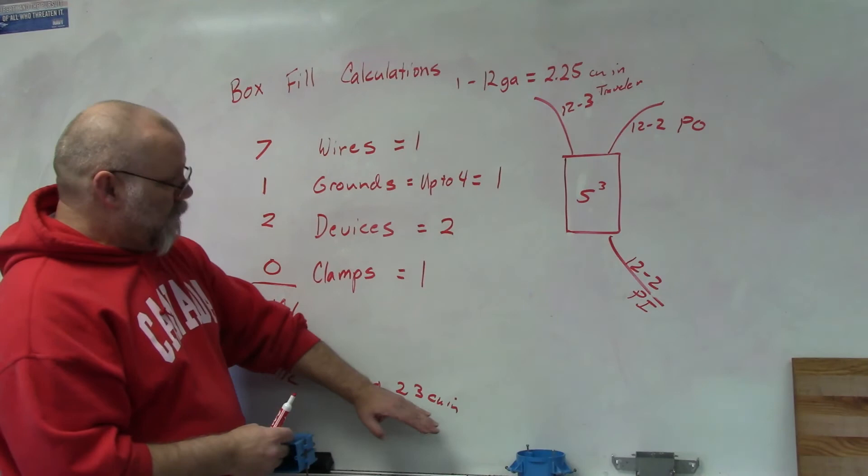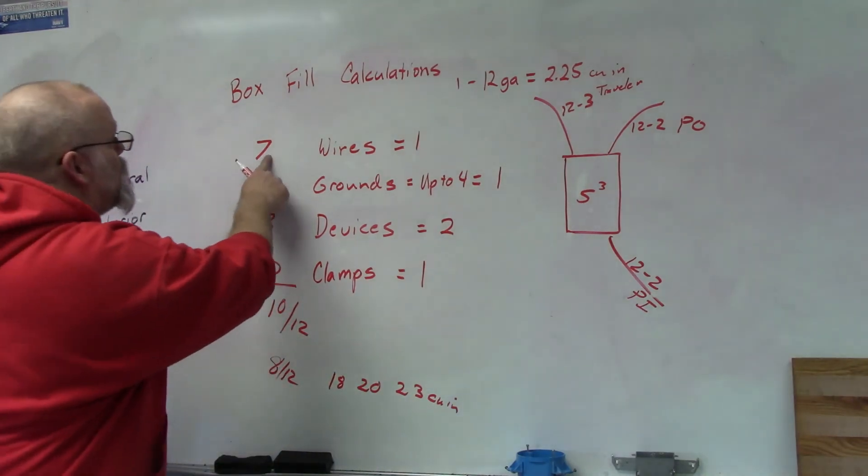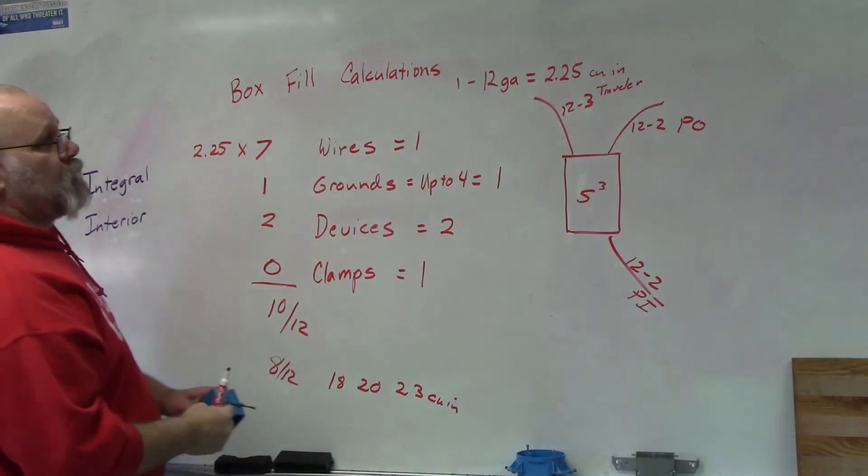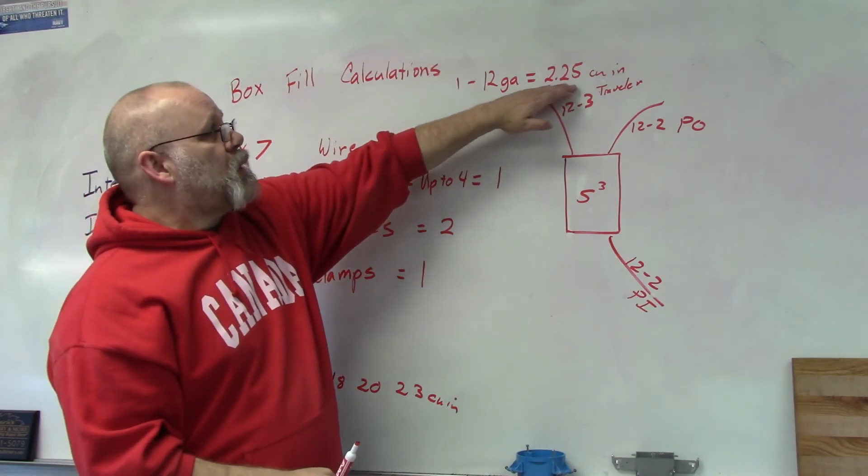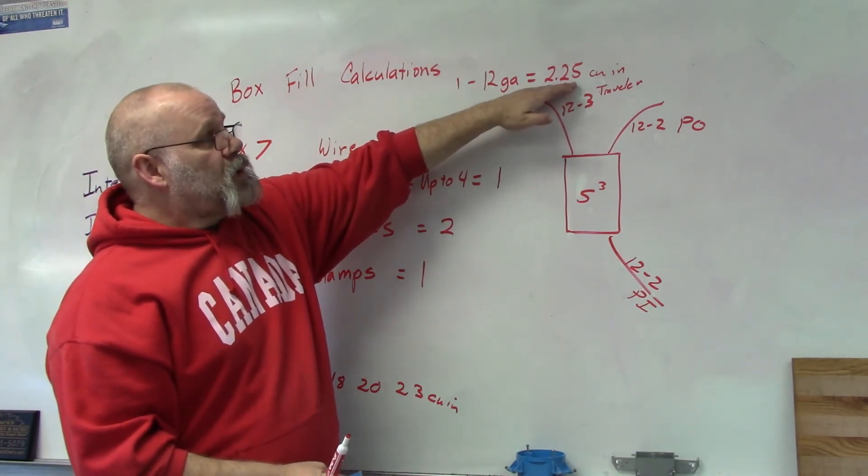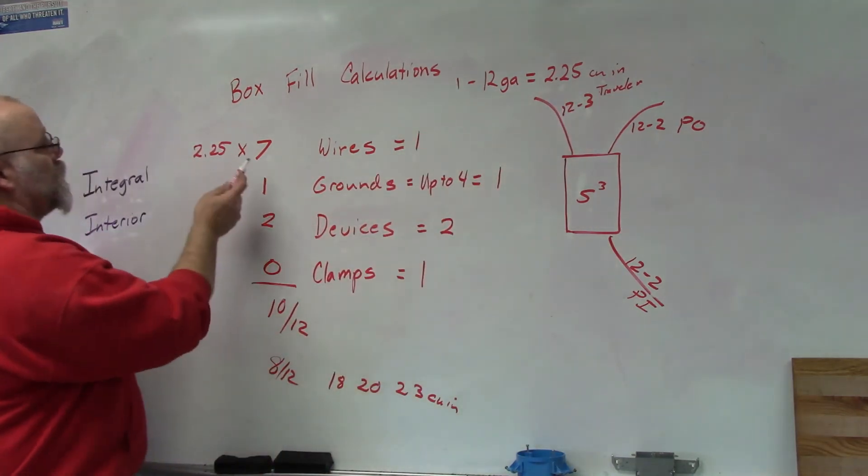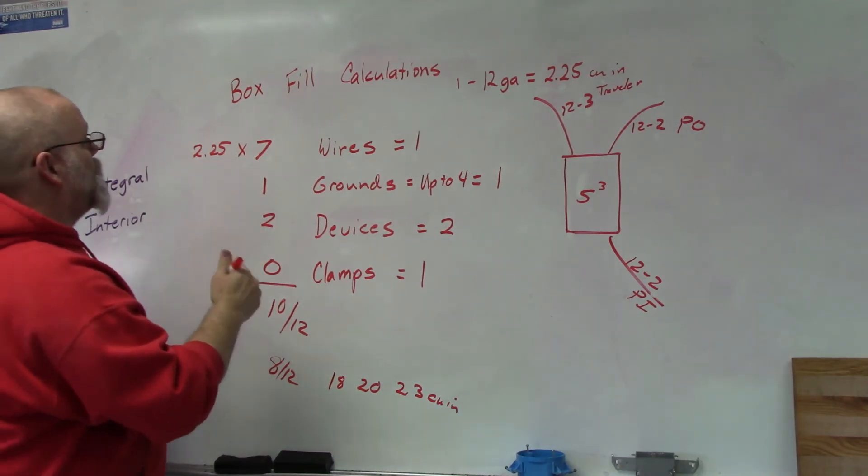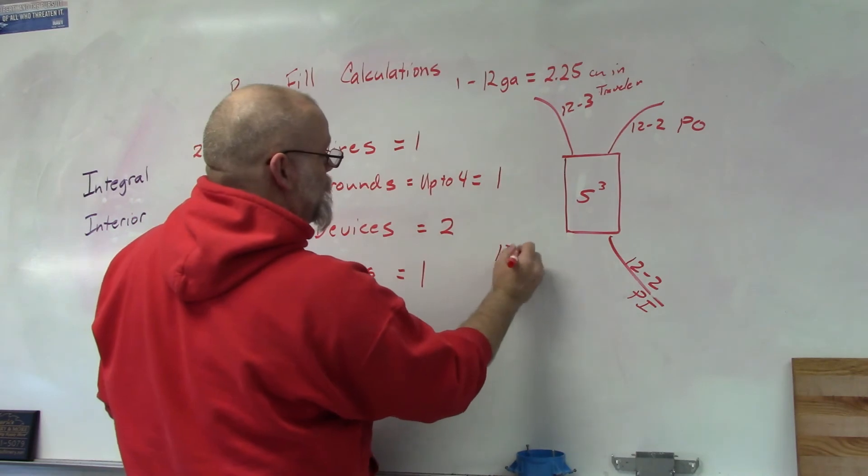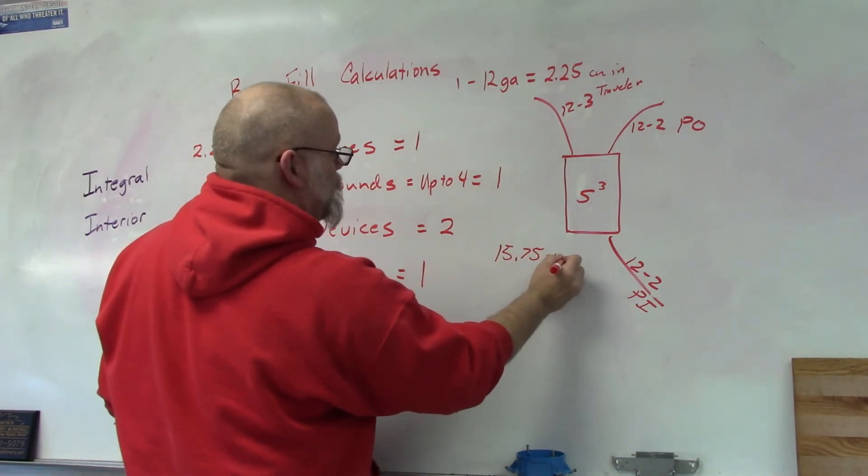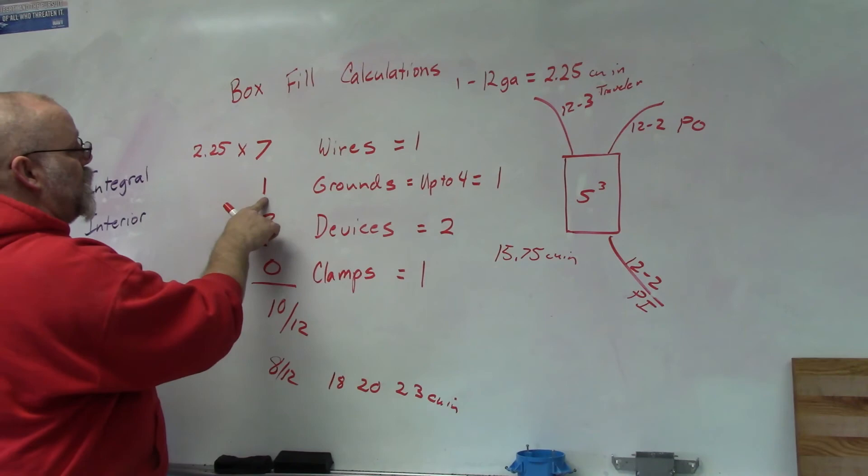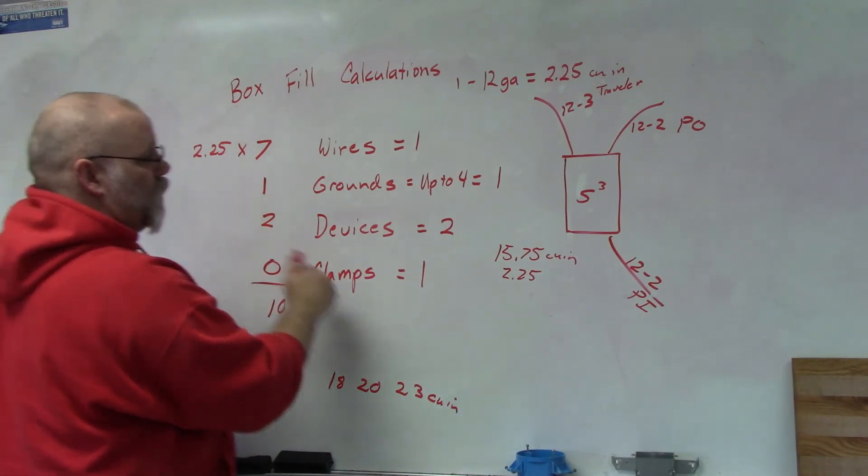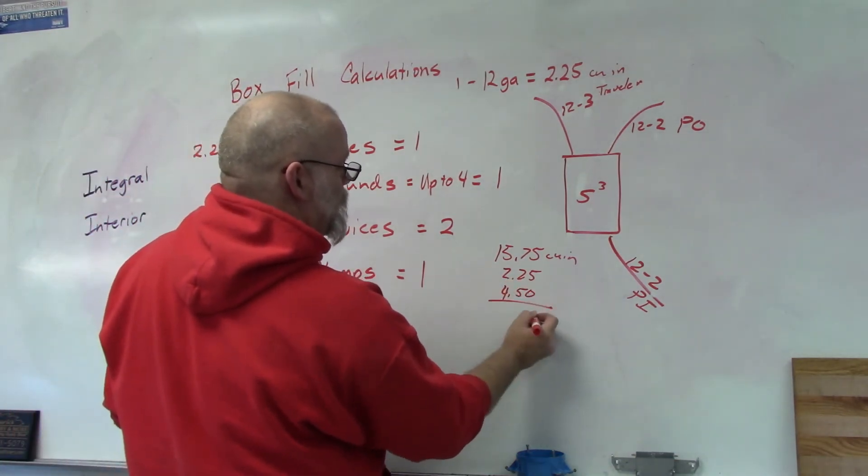So we can figure it out using the cubic inch method. All we'd have to do then is take this times 2.25 because 12 gauge wire is considered 2.25 cubic inches. So if I multiply these two numbers, seven times 2.25, I get 15.75 cubic inches. Then the grounds I would count as one, so I get 2.25, and then the device would be two, so that would be 4.5.